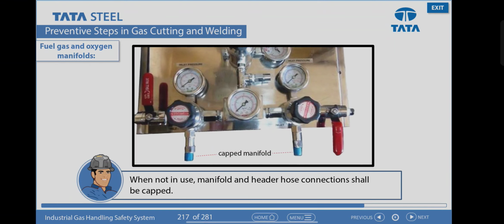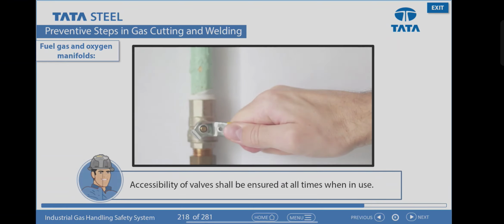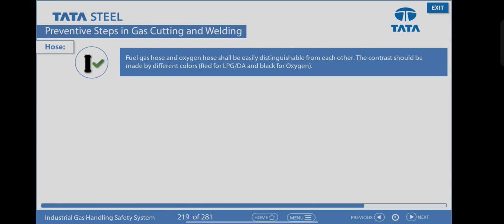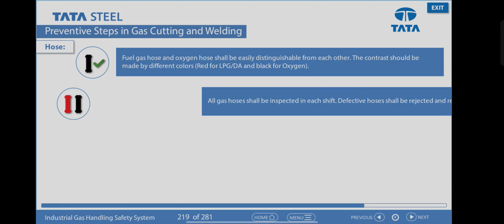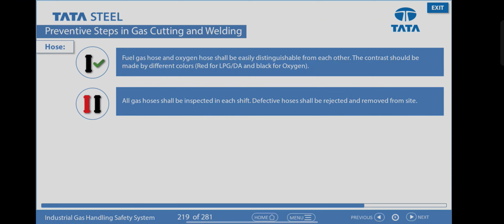When not in use, manifold and header hose connections shall be capped. Accessibility of valves shall be ensured at all times when in use. Fuel gas hose and oxygen hose shall be easily distinguishable from each other. The contrast should be made by different colors, red for LPG or DA, and black for oxygen. All gas hoses shall be inspected in each shift. Defective hoses shall be rejected and removed from site.